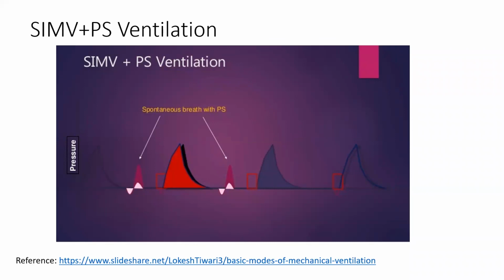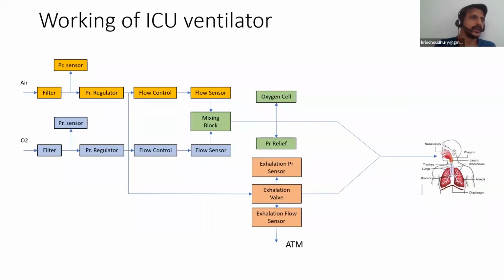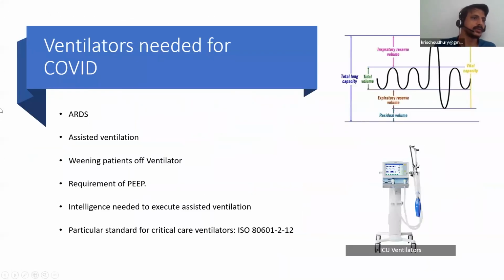You tell about the manufacturers, but when you test one of these ventilators, the first thing you need to do is buy a lung simulator. Any of the high-end ventilator manufacturers have a lung simulator. If I can get back to the slide, there's this ISO standard over here. The ISO standard calls for you to test it on that simulator.